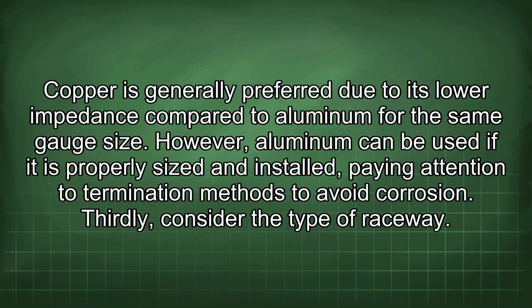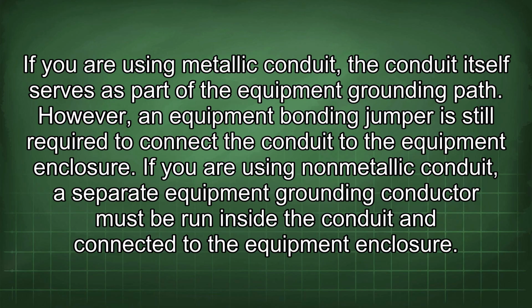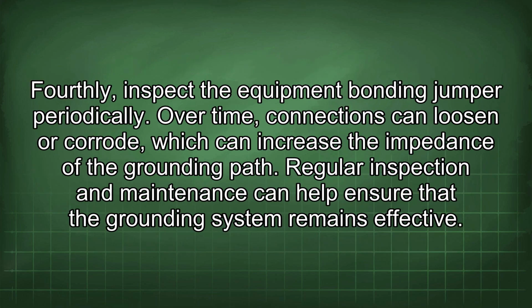Thirdly, consider the type of raceway. If you are using metallic conduit, the conduit itself serves as part of the equipment grounding path. However, an equipment bonding jumper is still required to connect the conduit to the equipment enclosure. If you are using non-metallic conduit, a separate equipment grounding conductor must be run inside the conduit and connected to the equipment enclosure. Fourthly, inspect the equipment bonding jumper periodically. Over time, connections can loosen or corrode, which can increase the impedance of the grounding path.